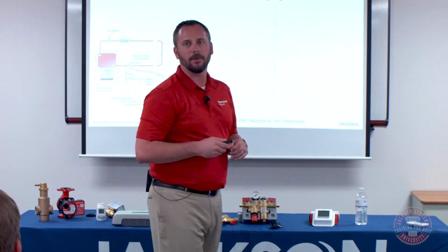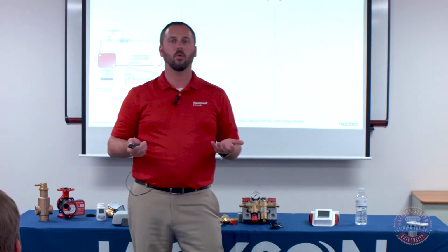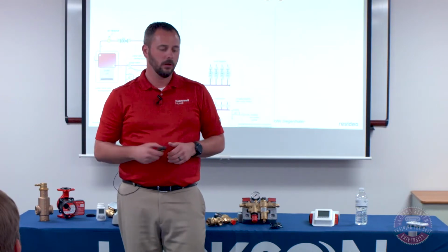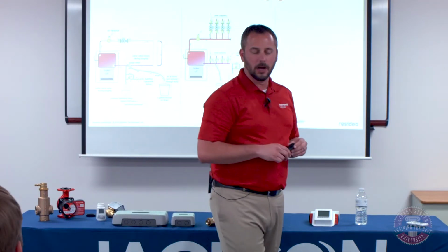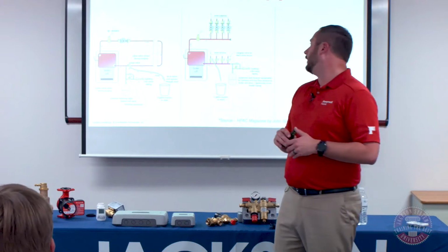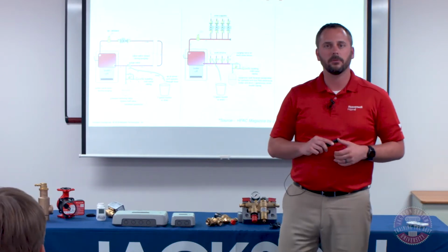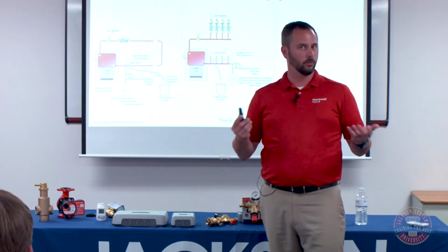That's a very effective way, but that's not real practical because we don't see a lot of one-zone hydronic heating systems. So this is much more common. And I'm showing a diagram here with 4 pumps. That could just as easily be one pump with 4 zone valves.